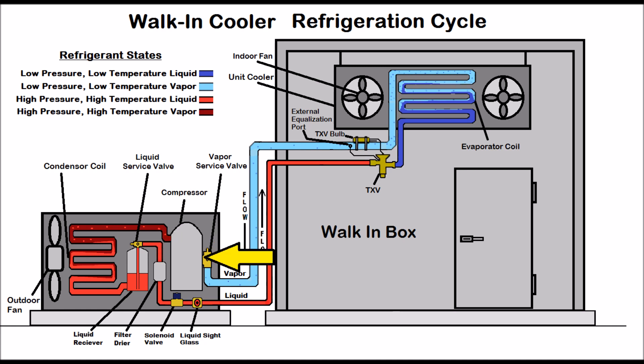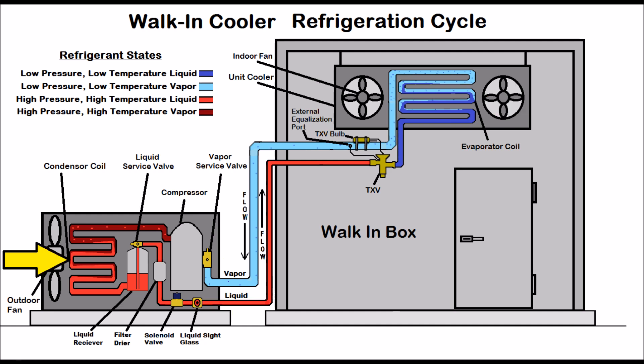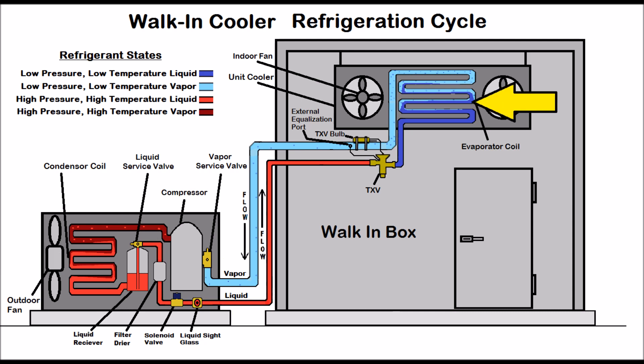So that's how it works — you're absorbing heat from inside the walk-in box and rejecting it outside. The liquid receiver is there because of the varying temperature load inside the walk-in box. You need more refrigerant when it's really hot inside and less when it's colder, so the liquid receiver stores the sub-cooled liquid refrigerant. Without a liquid receiver, liquid would be stored in the outdoor condenser coil, limiting the space available for the saturated state. The saturated state is where most of the energy is rejected out of the refrigerant and into the outside air, so having a large saturated state in both the evaporator and condenser coils is crucial.